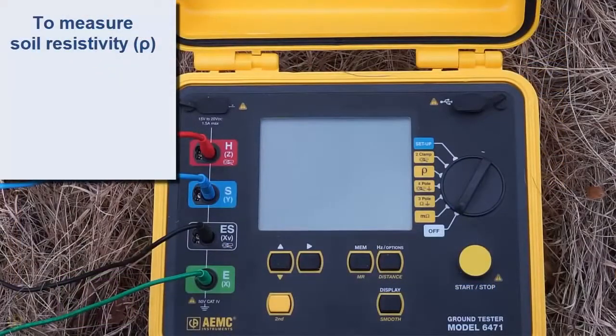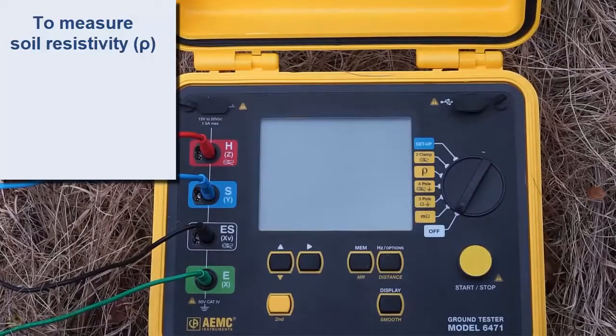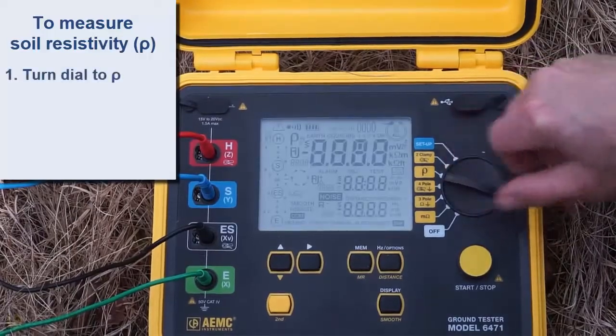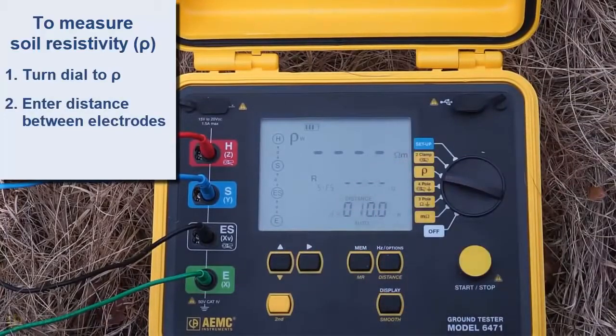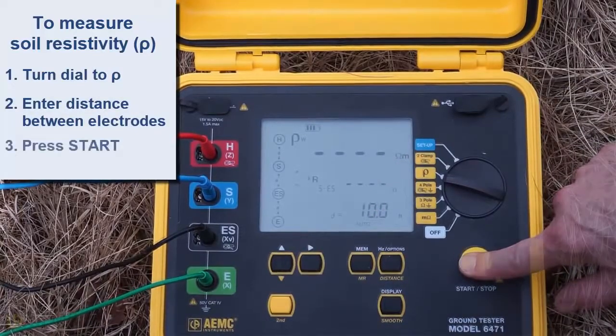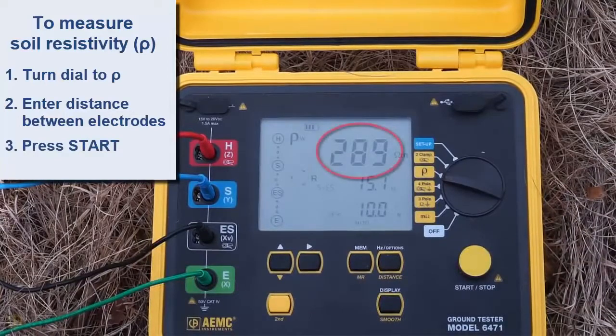The Model 6471 has the capability to automatically calculate and display soil resistivity, a value represented by the symbol rho (ρ). To measure this value, turn the dial to the rho setting and enter the distance between electrodes as instructed by the instrument's user manual. Then press the START button to take a measurement. After a few moments, the resistivity reading appears. If you regularly need to perform soil resistivity testing, consider purchasing an instrument such as the Model 6471 that automatically calculates this value.